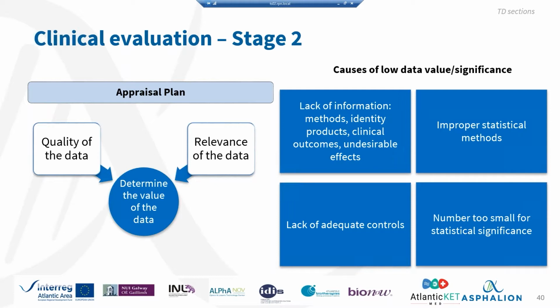And also, number two is more for statistical significance. There are also quite a lot of publications that are based on 10 or 20 patients, and obviously that's not enough to justify the safety of your device. Even if the publication is from a device that can be considered equivalent to your device, and it's being used for the intended use of your device, if the number is too small, like it's been used in 10 patients, it won't suffice to claim safety of the product.